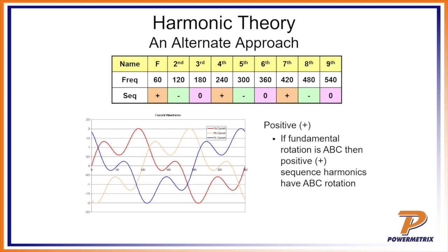What it means from a more practical point of view is to look at how those different harmonics affect a motor, for example. A positive harmonic, which once again would be our fundamental, our fourth or seventh. If we think about an AC motor that's turning in a certain direction, and we start to have a load that's generating those positive harmonics, what that's going to do is actually try and make that motor run faster. It's trying to push the magnetic envelope so that it's going a bit faster, which of course isn't really good for the motor. If you're trying to keep it regulated, that's a problem.